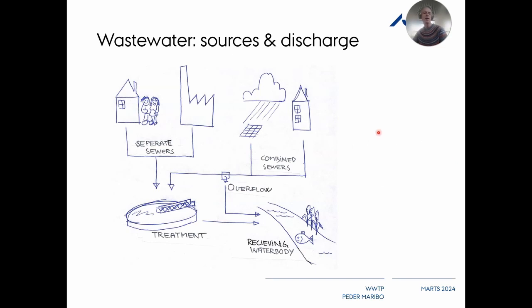Another thing to look into is what kind of sewer system we've got. The main difference is whether we have separate sewers or combined sewers including stormwater. From a combined sewer system, first of all we have overflow structures to minimize the peak hydraulic load at the treatment plant, but in any case there will be a considerably bigger difference from dry weather flow to peak flow in a combined sewered area. That is an important issue.